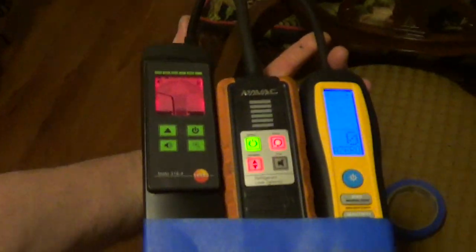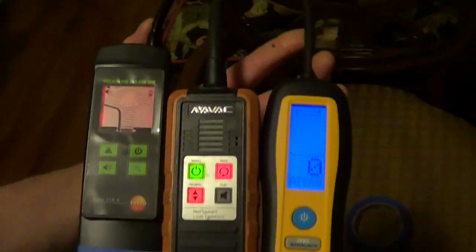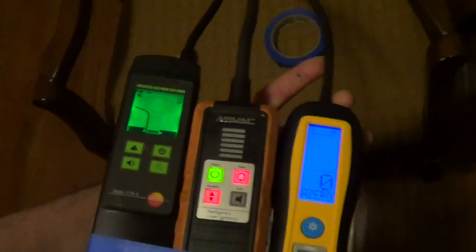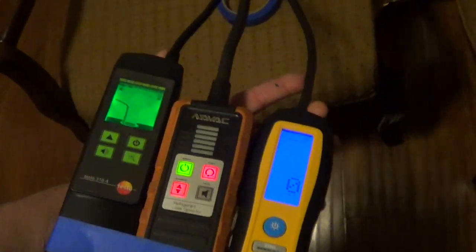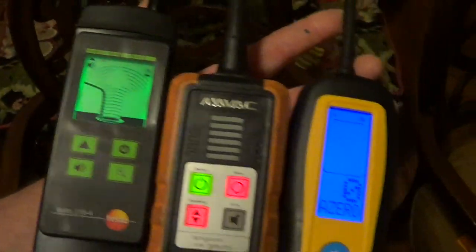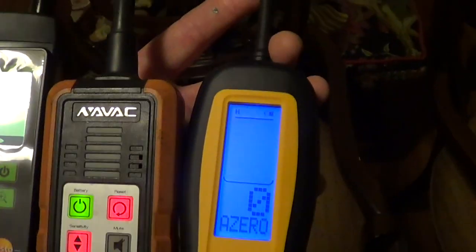It seems like the Testo is more sensitive to nuisance trips. So let's go around and check things that are not leaking right now, and see which ones are nuisance tripping. I am on high sensitivity on everything. The Testo and the Navac are green, and the Fieldpiece is on H.